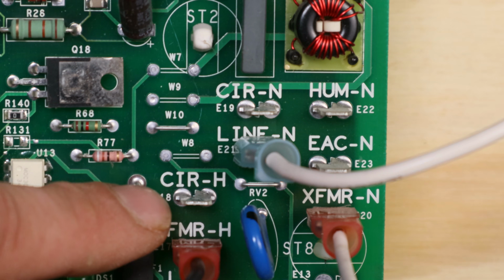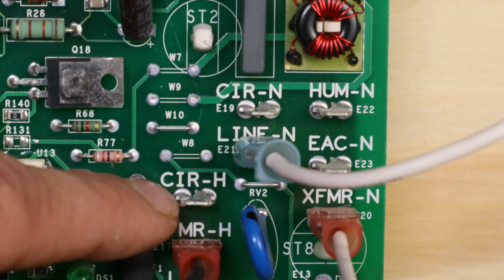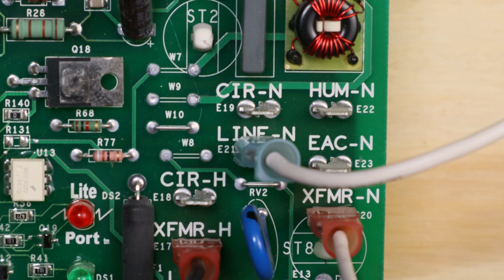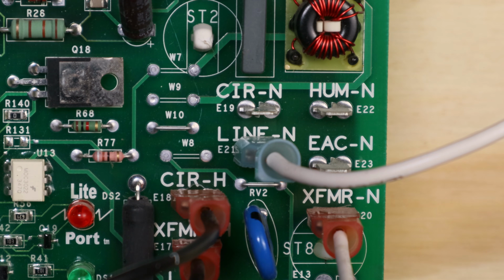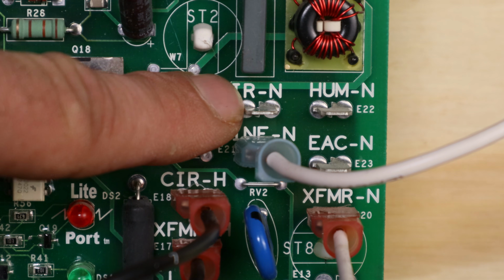Now over here, we have a pin that says CIR-H. That's our circulator blower or blower motor. That's our hot, or 120 volts. So the black wire from that Molex plug will go right there. And then our neutral goes back to the circ N. That's our neutral there.